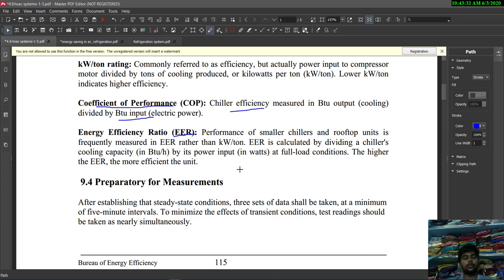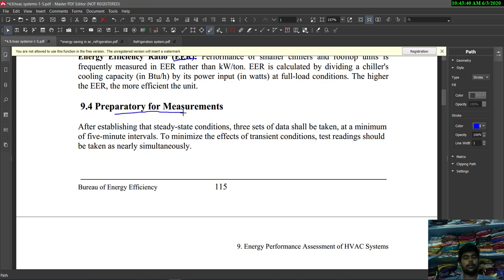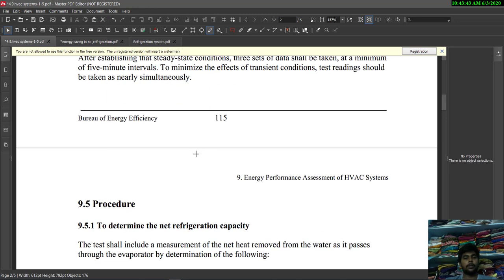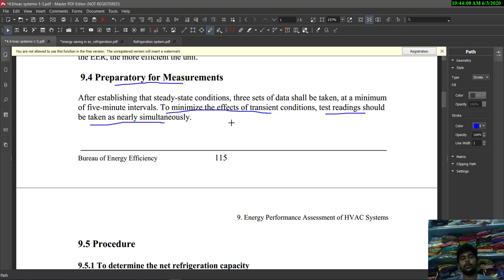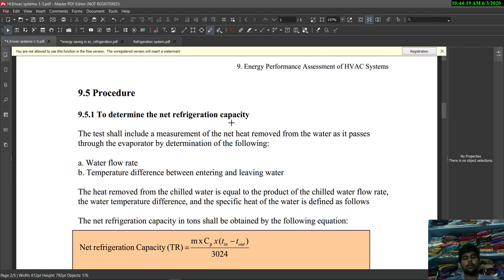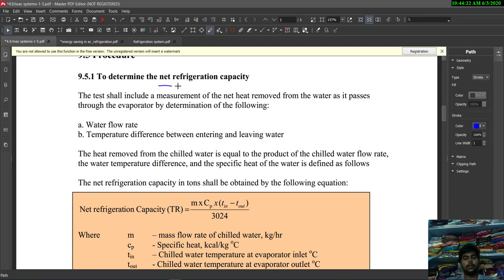Next is preparatory measurements. To minimize the effect of transient conditions, test readings should be taken as nearly simultaneously as possible. We have to monitor transient and varying conditions and note down readings related to surrounding temperature and conditions. The procedure is to determine the net refrigeration capacity.